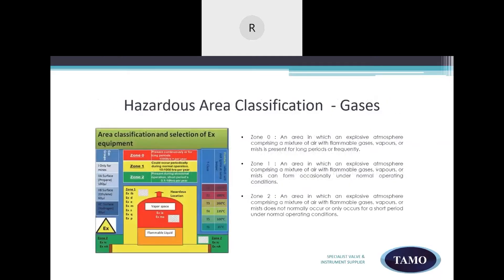Let's look at the hazardous area classification of gases. Releases of flammable gases and vapors will usually result in flammable atmospheres. And these areas are classified as Zone 0, Zone 1, and Zone 2. Zone 0, where flammable atmosphere is present continuously for long periods. Zone 1, where a flammable atmosphere is likely in normal operation occasionally. And Zone 2, where an explosive atmosphere is present less than 10 hours per year.